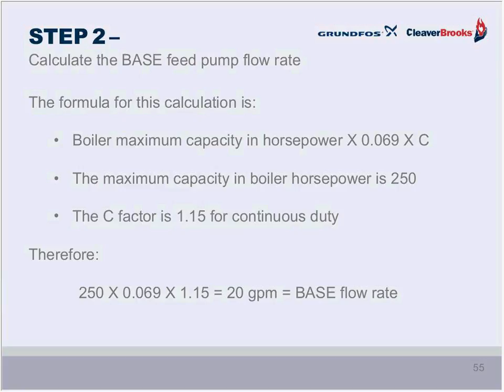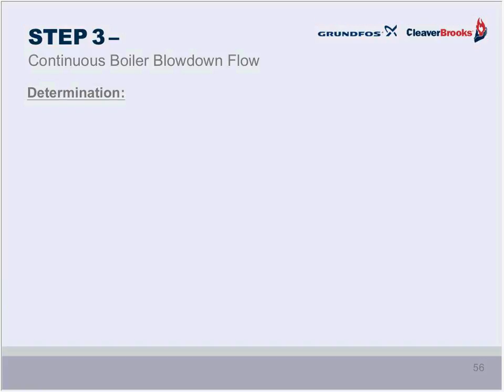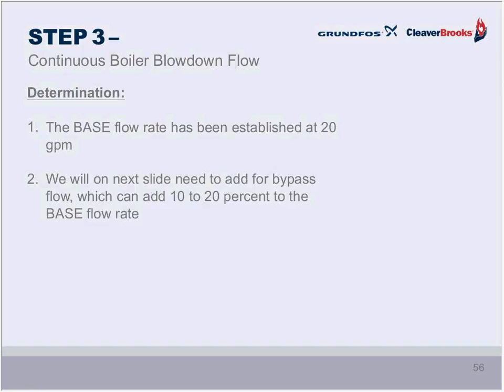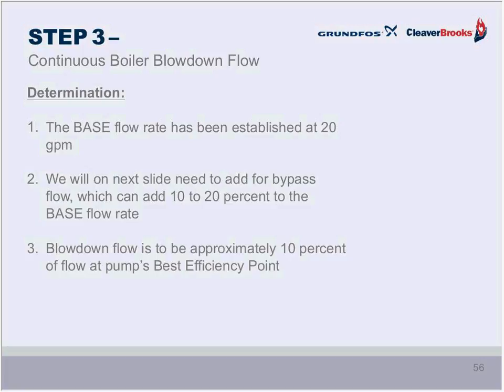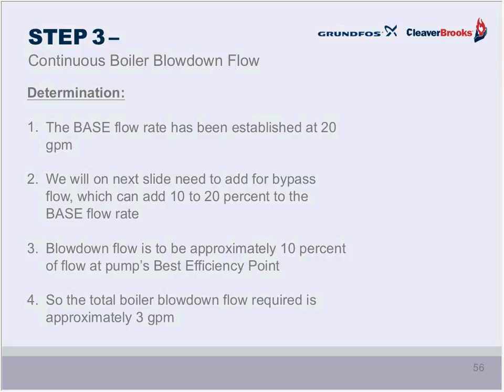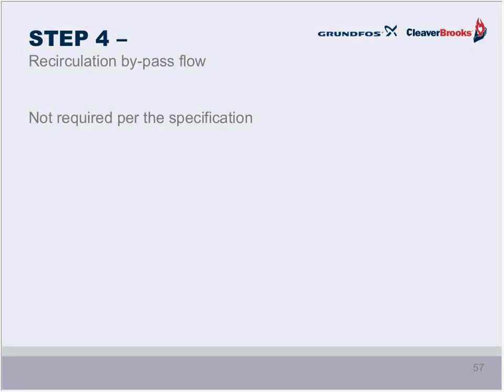Now we have to add to that if we have continuous boiler blowdown flow, which was explained in some detail in the first webinar. We have a base flow rate of 20. If we need to add bypass flow, which we're not going to in this case, that would add even more. The continuous boiler blowdown flow, to get rid of total dissolved solids, is usually about 10% of the pump's flow at the best efficiency point. So we need somewhere around 2-3 gallons per minute. And that value, by the way, will be set by the water treatment people. There's no recirculation bypass flow. That's for step number 4, so we don't have to calculate for that.